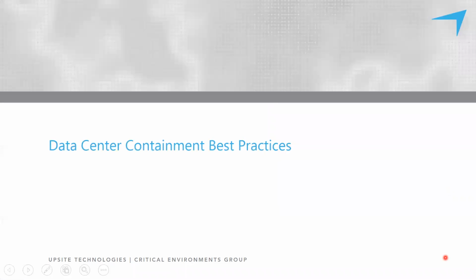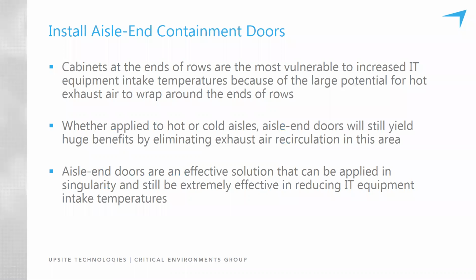Nice. Thank you, Rob. As we move from sealing smaller openings to larger and larger openings, let's start talking about doors, what everyone thinks of when they think of row containment. Doors are particularly important because cabinets at the ends of rows are really vulnerable to exhaust air recirculating around the end of the row and causing elevated temperatures for the equipment in the cabinets at the end of the row. And doors are hugely beneficial whether or not a roof is installed.